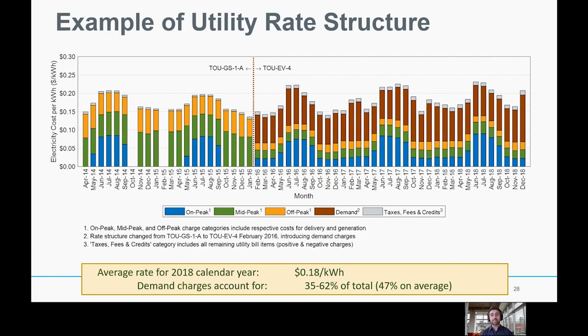At that peak period, they may have been consuming somewhere in the range of 20 to 40 kilowatts, and for most of the rest of the month it might have been an average of 10 kilowatts. When you have a peaky demand with large spikes at certain periods of the day, that presents a great opportunity to level your overall load profile, reduce those peaks, and mitigate those demand charges.